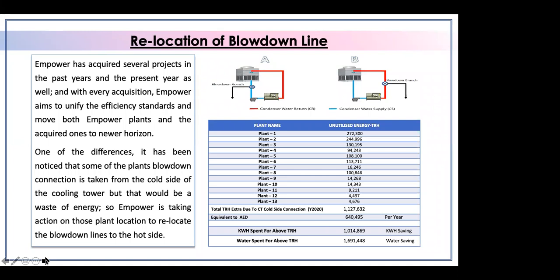What is happening here, if we are in type A, the chiller cools the outlet, and the cooling tower cools the return water to the cooling tower. This energy, which has been cooled, a portion of it is being drained out as blowdown, and we lose energy from it. So this has been identified, and we are in progress of shifting it to figure B, where the blowdown will be taken from the return water of the cooling tower. Anyways, that's energy that is being returned back to the cooling before it gets cooled down.